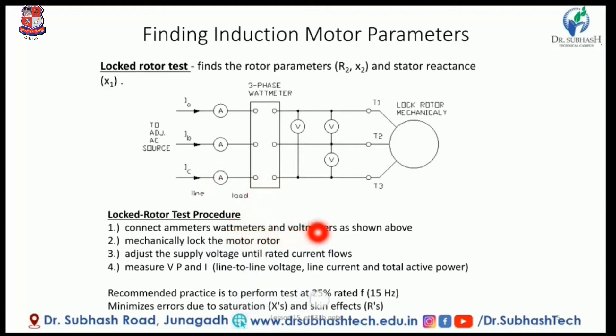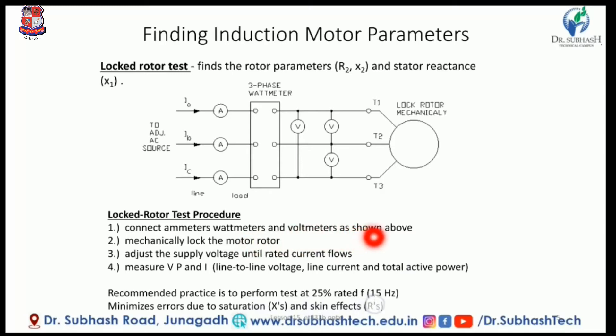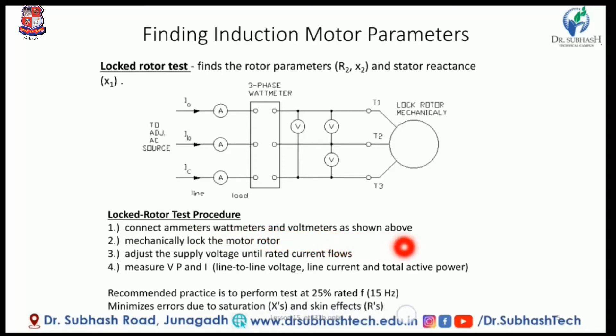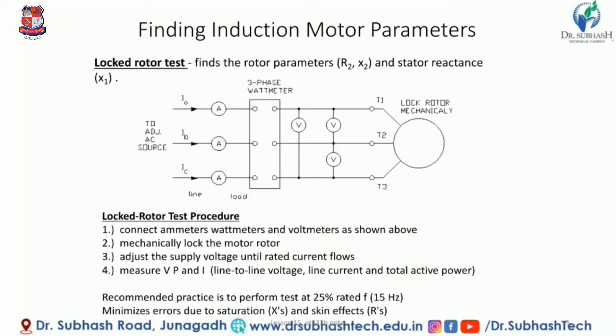Mechanically lock the motor rotor. Adjust the supply voltage until the rated current flows. Measure voltage (line-to-line), current, and total active power. The recommended practice is to measure line-to-line voltage, power, and current at reduced voltage corresponding to rated current.